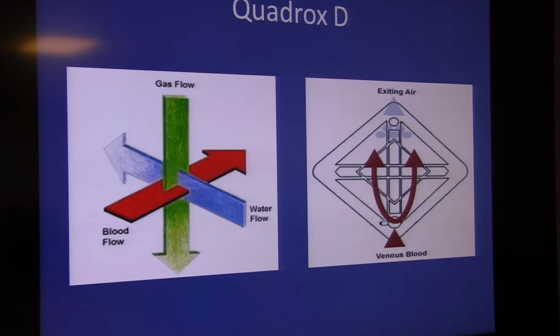and it comes around here, you get to a flow meter like you guys are used to seeing for nasal cannula with a blender associated with it. So this is your gas source in. So gas source in at the top. If it goes in at the top, it must therefore come down and out the bottom. Down here at the bottom, it's confusing because there's this one piece right here that's just a stand. This is actually the exhalation port of the oxygenator.